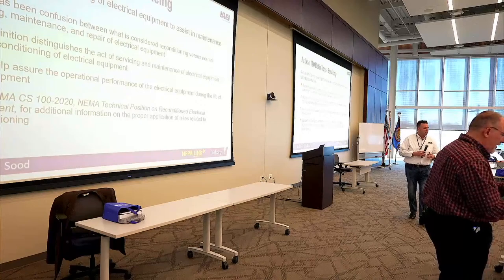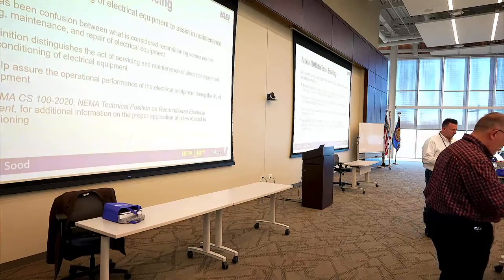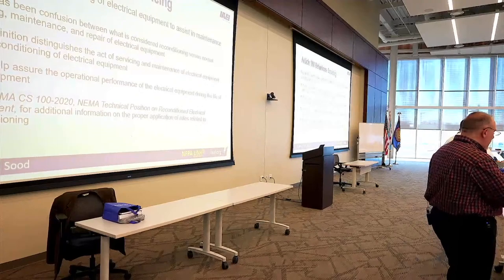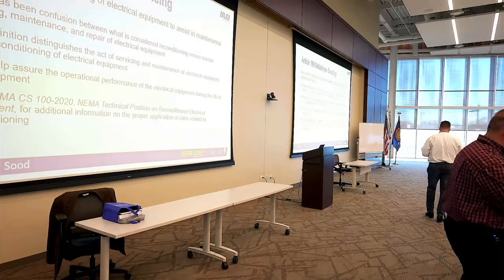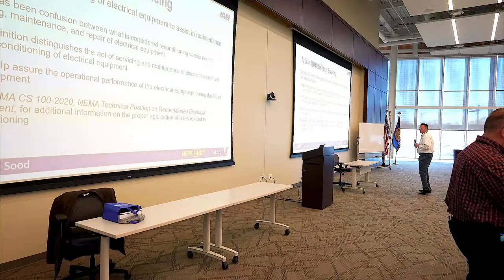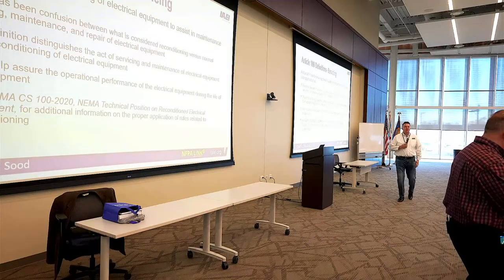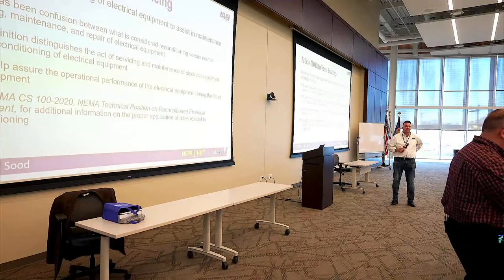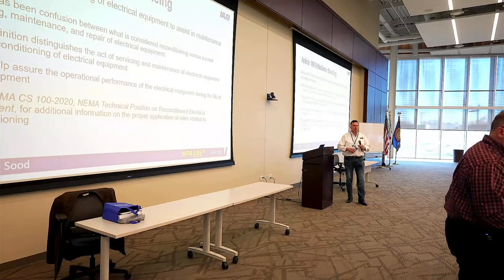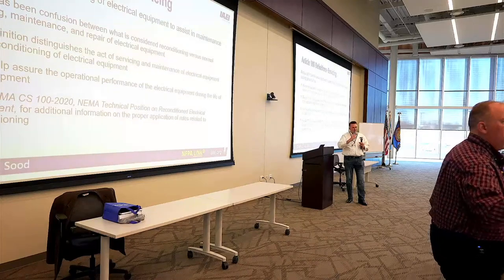110.17? 110.17, thank you, my walking code book. 110.17, servicing and maintenance of equipment. Servicing and electrical preventative maintenance shall be performed by qualified persons trained in servicing and maintenance of equipment. So you better be qualified. The servicing and electrical preventative maintenance shall be performed in accordance with the original equipment manufacturer's instructions. So the moment you go outside of the instructions, you are now possibly reconditioning it.